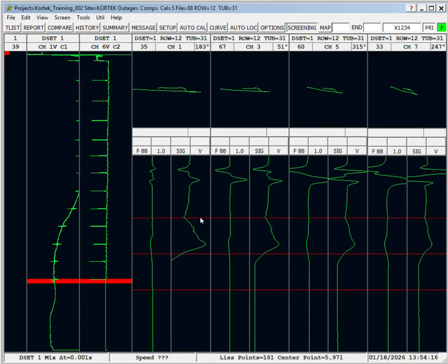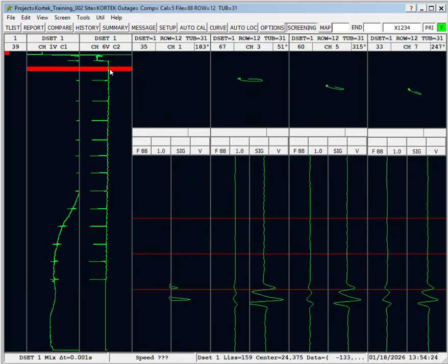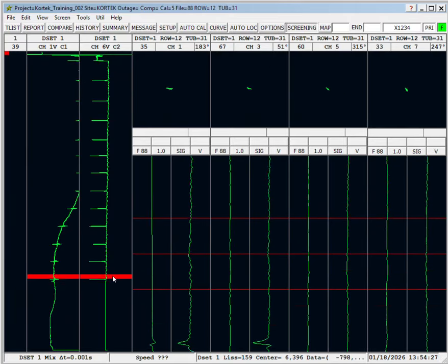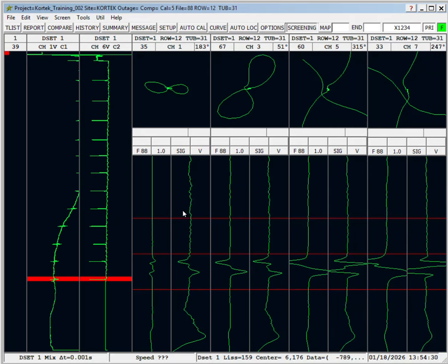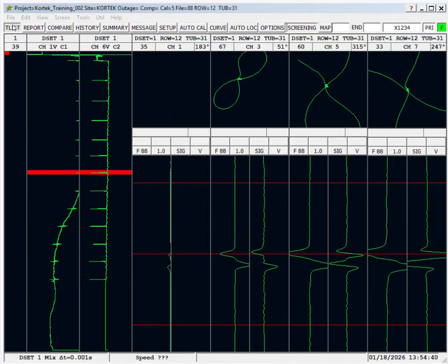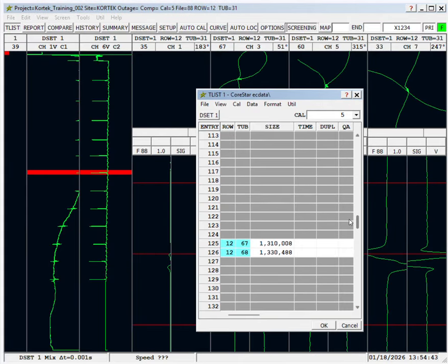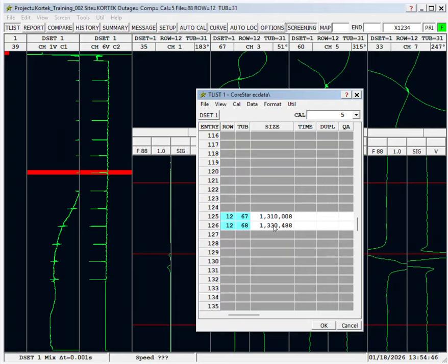What you see here, these are U-bend tubes, but because the bend radius of the U-bend's too tight, the acquisition team only puts in the probe up until they hit the bend region, and then they stop. So this is only a partial recording of the tube because they couldn't get full length because they couldn't get over the U-bends. All right, so hopefully you're starting to see a pattern with some of these dent signals. Dents by themselves are not discontinuities. There's no degradation of the tube. It's just that there is a reduction in the tube ID. It's a change to fill factor, essentially.